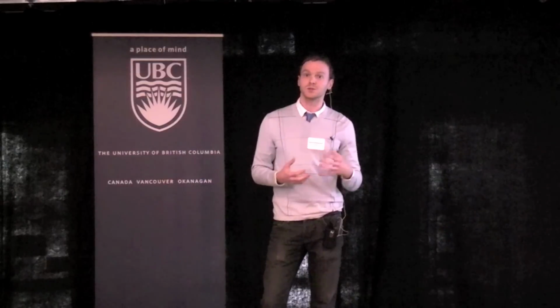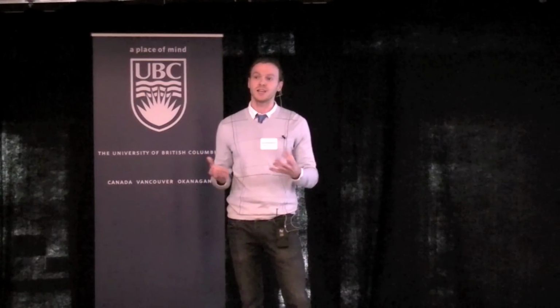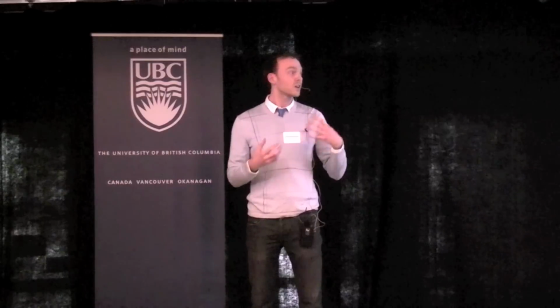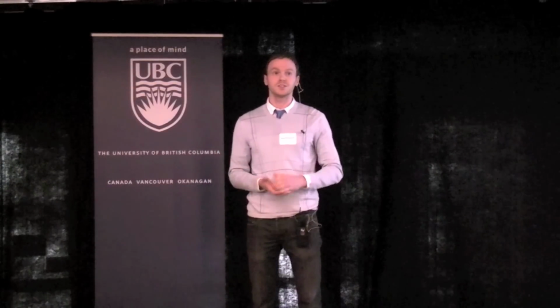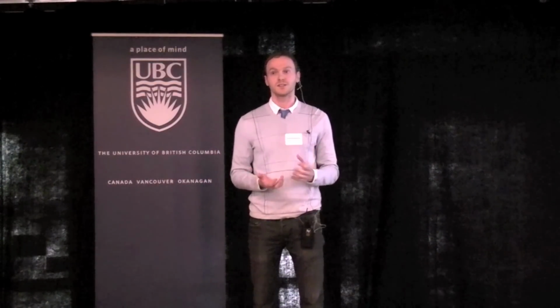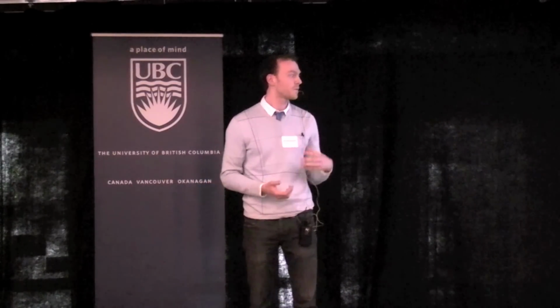What this allows me to do is to compare different filters from different manufacturers installed in any system, anywhere in the world, and to determine which is the most energy efficient at removing particles. It also allows me to look at different ways of controlling and operating our air handling systems to improve upon the energy efficiency and indoor air quality inside buildings. And finally, it allows us to produce a standard for comparing filter energy efficiency, a standard which, surprisingly enough, doesn't exist anywhere in the world.